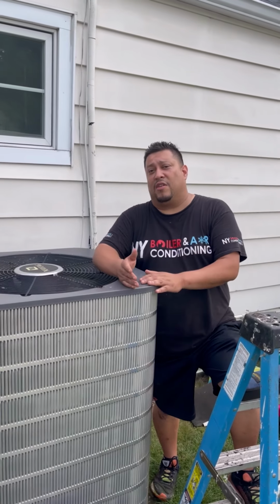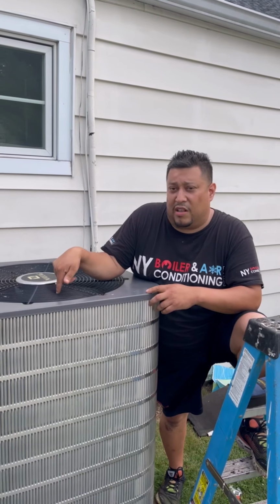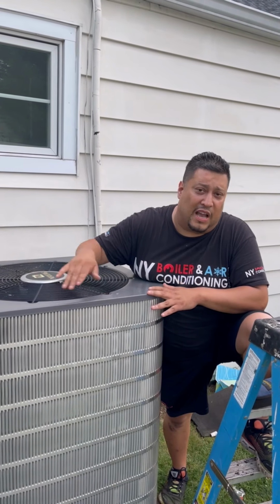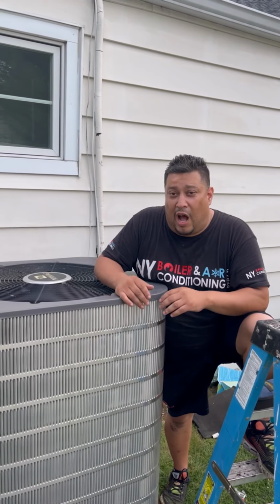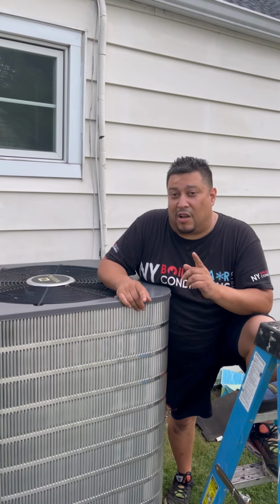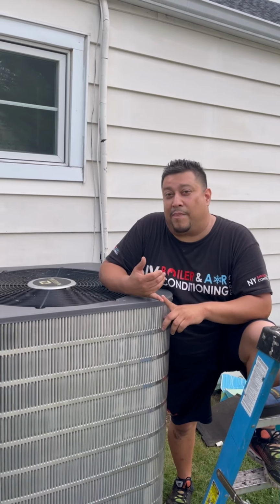I check everything. So first thing is first, I check this power. Obviously this power, I'm getting 24 volts from the indoor unit to the contactor. So I put that to the side. Now we check the high voltage. But before I check the high voltage, I also check the capacitor, because the capacitor sometimes gives you those type of symptoms. I checked the capacitor, it was a little weak.